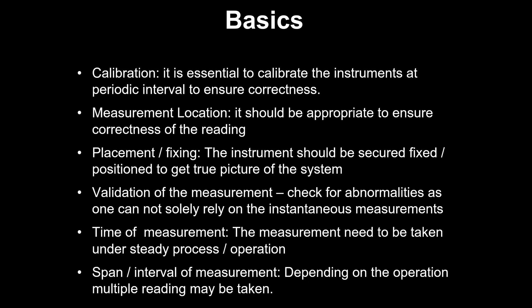Duration is the same way. Earlier it was time, then we said duration. If it is required to be logged, we log it. This logging also becomes critical for, say, textile and pharma industries, where they are trying to monitor temperature and humidity. There are now temperature humidity loggers available, which are not very expensive. We leave them inside, even in a data center, because measuring for a few minutes is not going to give you the correct value. So we place the data loggers at appropriate locations and capture data for 24 hours at maybe 1-minute or 5-minute intervals, to see the variation or profile. Based on that, many times suggestions can be given.